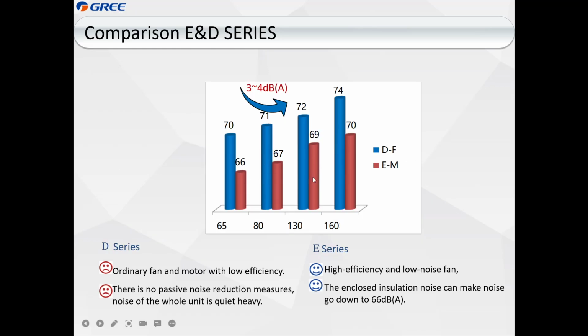Yes. This noise data, we test the distance at 1 meter from the unit, and the height is in the center of the unit, for example half of the height of the unit. And the distance is 1 meter.